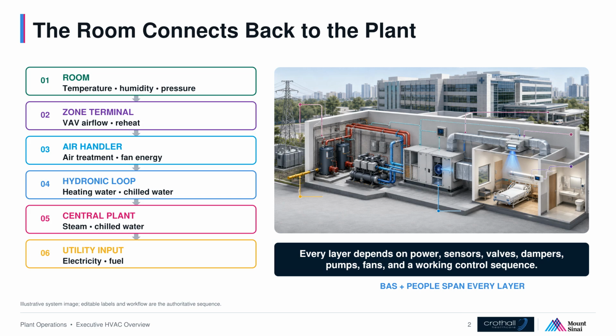Pick one patient room and work backward. The room needs the right temperature, humidity, airflow, and where required, pressure relationship. A variable air volume terminal meters airflow and may add reheat. The air handling system filters, heats, cools, dries, humidifies, and pushes the air. Heating water and chilled water loops connect that equipment to the central plant. The plant, in turn, depends on electricity and fuel.